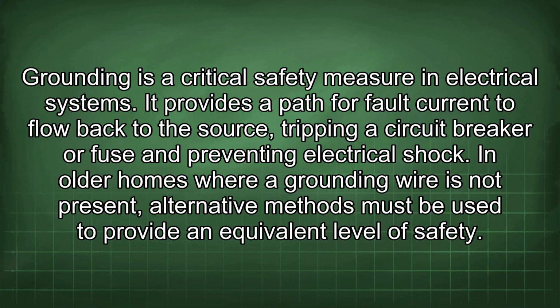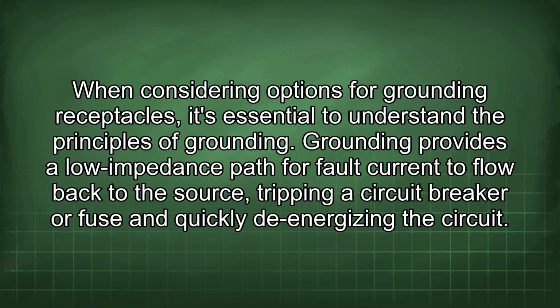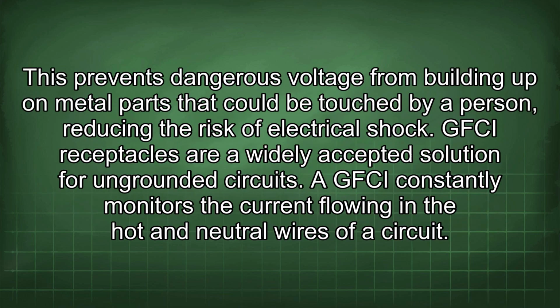When considering options for grounding receptacles, it's essential to understand the principles of grounding. Grounding provides a low impedance path for fault current to flow back to the source, tripping a circuit breaker or fuse and quickly de-energizing the circuit. This prevents dangerous voltage from building up on metal parts that could be touched by a person, reducing the risk of electrical shock. GFCI receptacles are a widely accepted solution for ungrounded circuits.